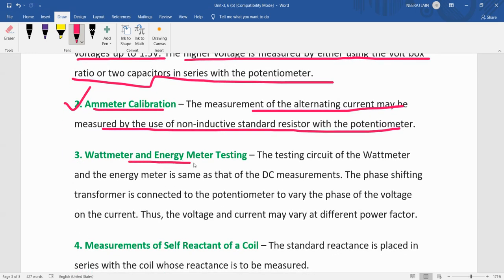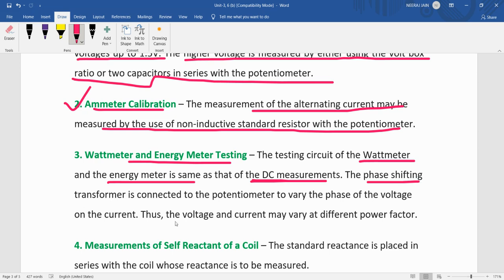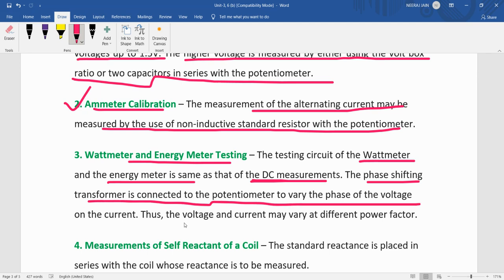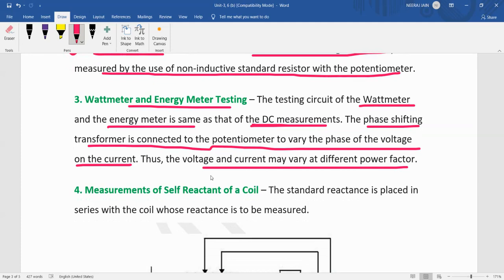Wattmeters and energy meters can also be calibrated, similar to how it is done in DC measurement. A phase shifting transformer is connected to the potentiometer to vary the phase of the voltage or current, so the voltage and current may vary at different power factors. Using different power factors with the phase shifting transformer, we can measure the power factor and perform testing of energy meters and wattmeters.